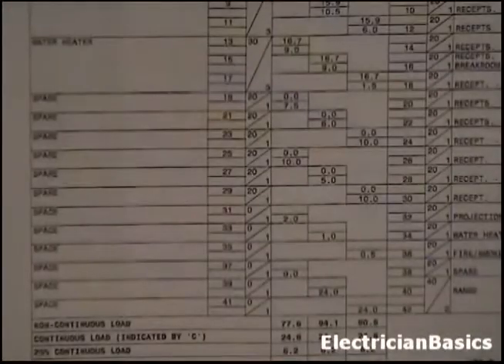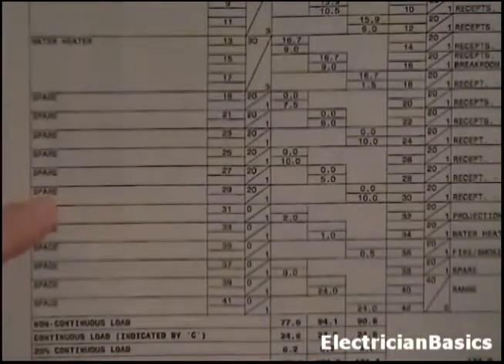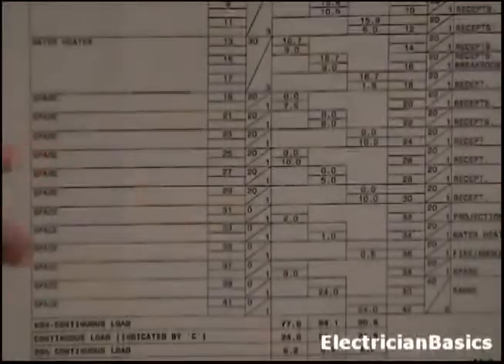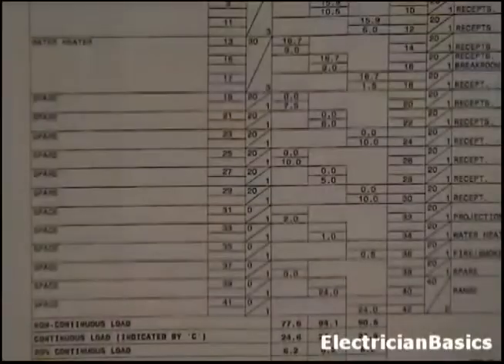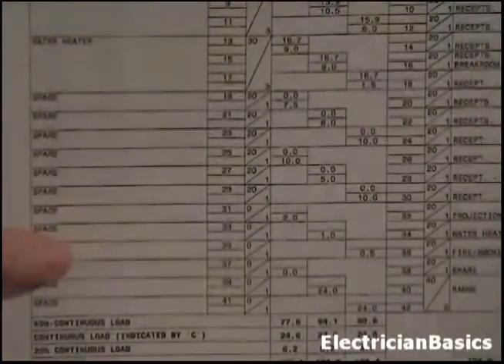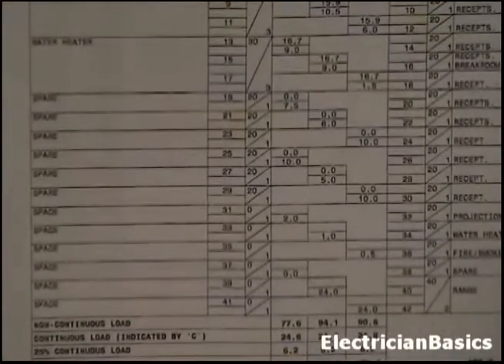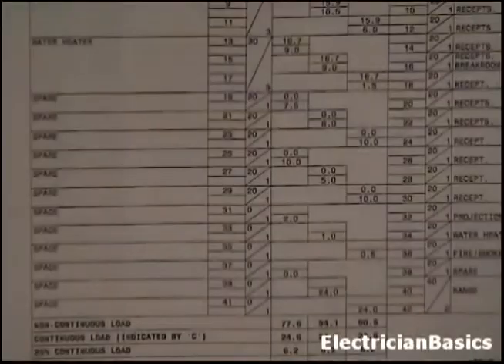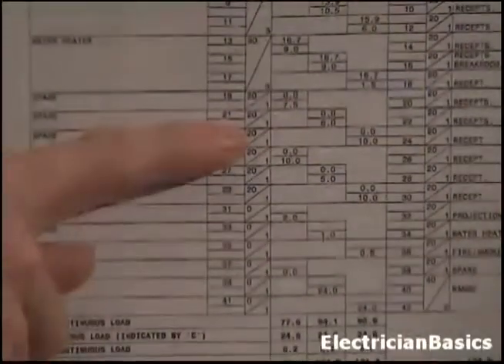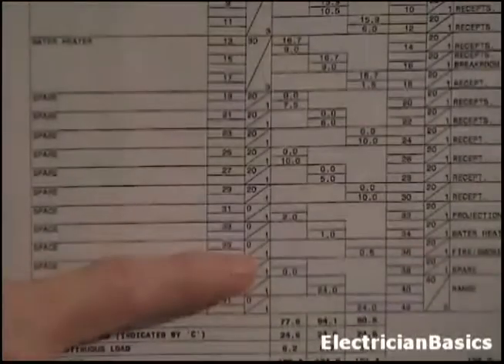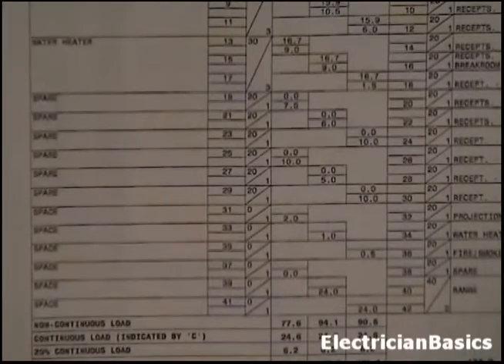Underneath water heater we have spare, spare, spare, spare, spare, spare. And these are breakers that are put into the panel in case you need a spare. They're going to assume, like in most places, you add things. So they give you extra breakers there so you can add those things. Now underneath spare we have space. Okay, space, space, space, space, space. Now a space is just a space. There is no breaker there. A spare, you have to have a breaker. So if you look at it over here on this side, on the spare, see it's 20 amps on that breaker. You go to a space, it's 0. Okay, because there is no breaker there.